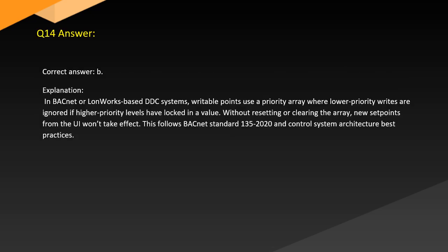Answer. Correct answer: B. Explanation. In BACnet or LonWorks DDC systems, writable points use a priority array, where low priority writes are ignored if high priority levels have locked in a value without resetting or clearing the array. New set points from the UI won't take effect. This follows BACnet standard 135-2020 and control system architecture best practices.